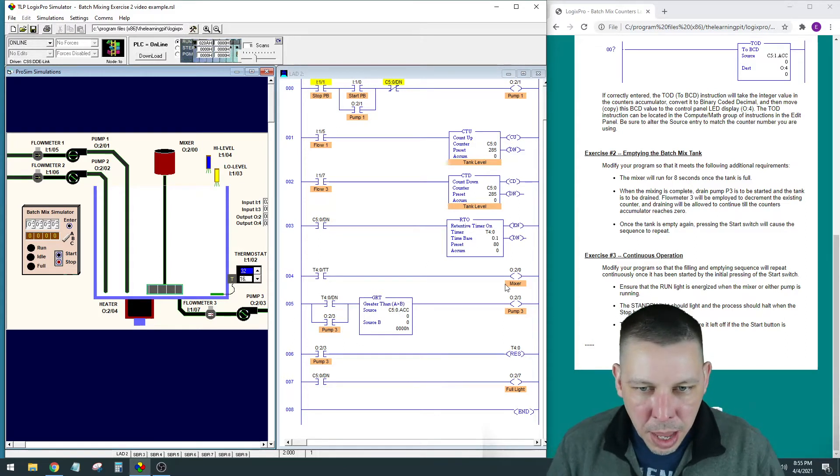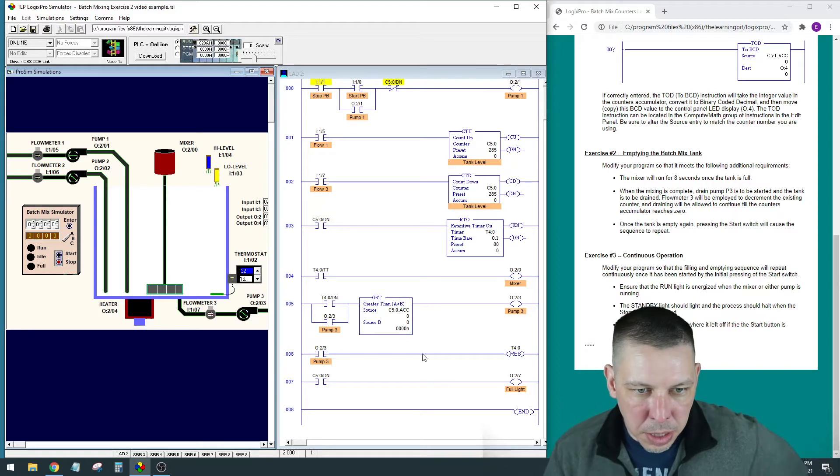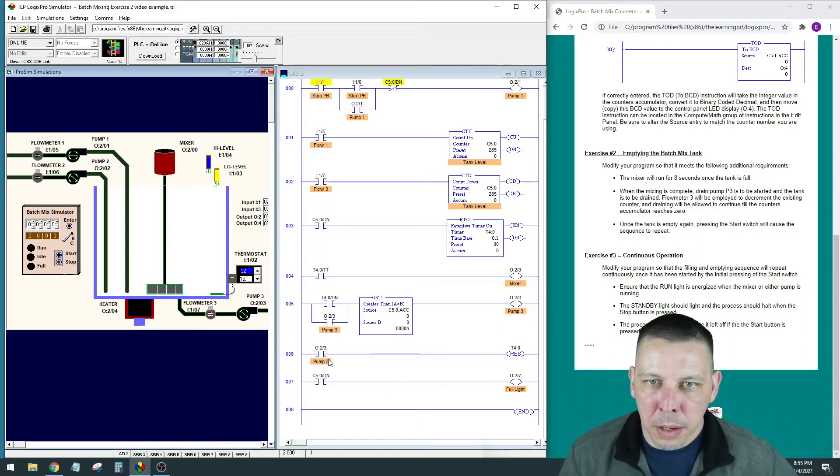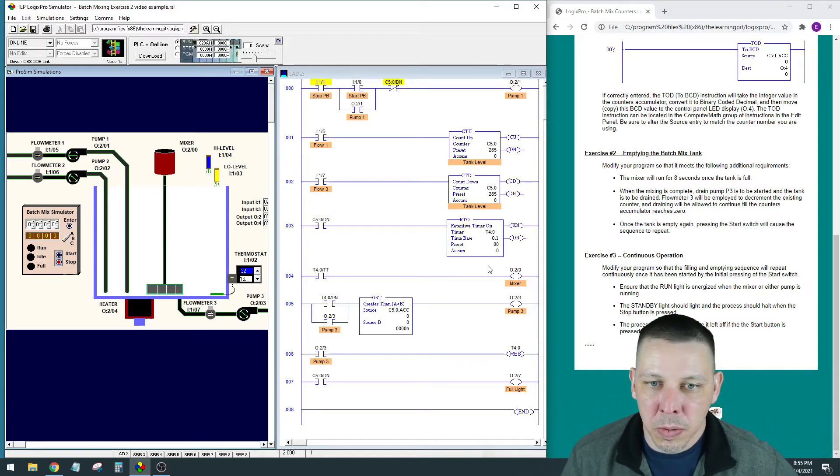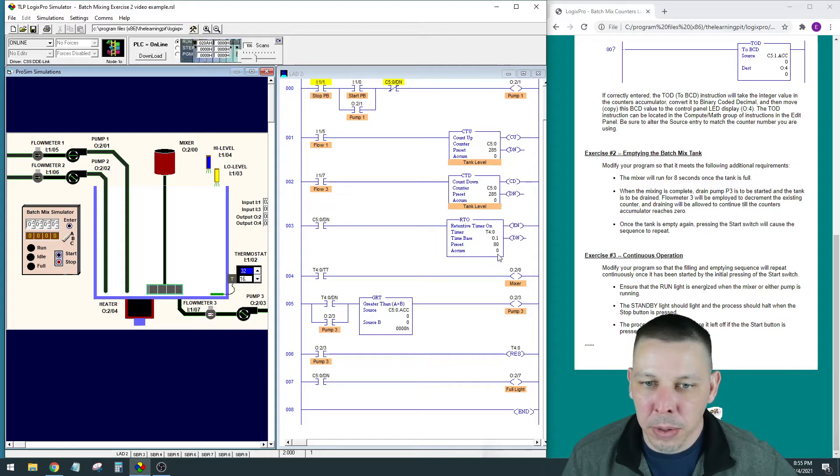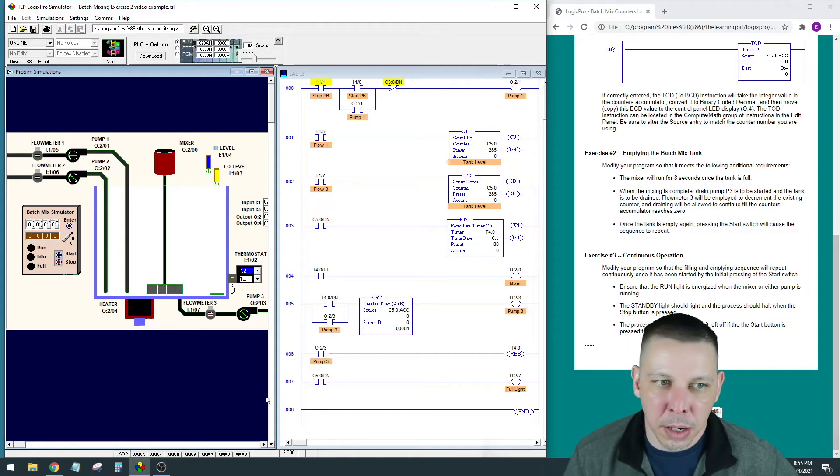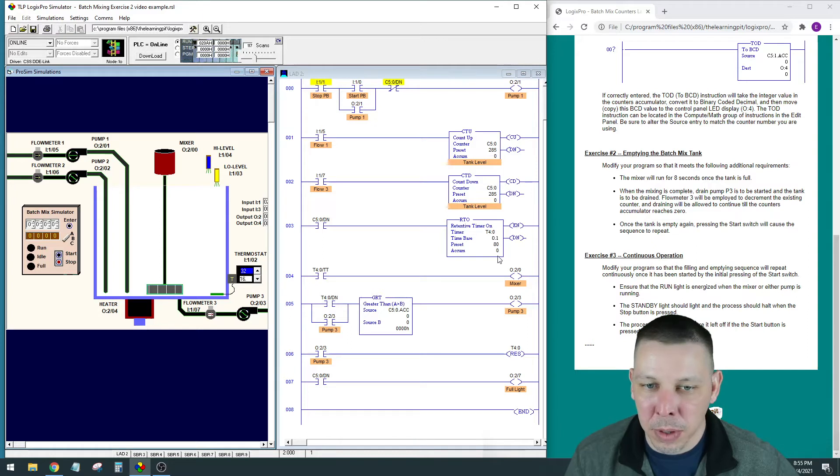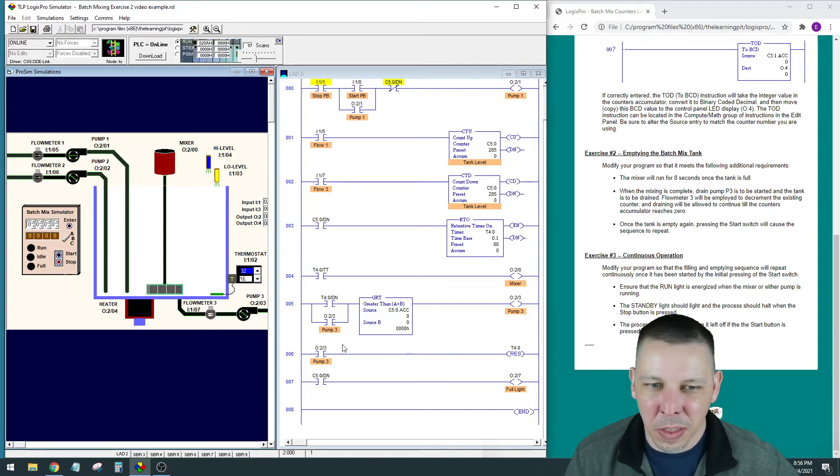That change—because before I had this set to pump one—so this retentive timer would hold that value in the accumulated in between runs, and then the next time you started it would start out with a value in the accumulated, and that's just not the cleanest way to do it.